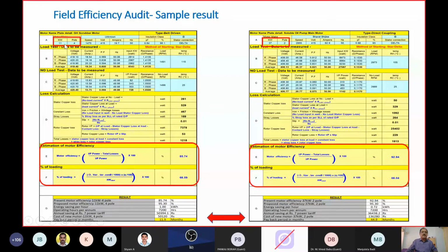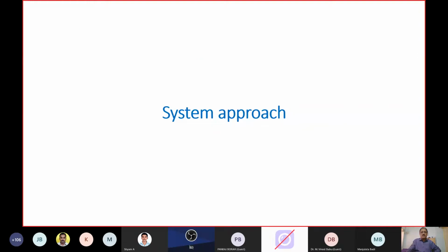In this case, it is an 11 kilowatt 4-pole motor. In this case, it's a 37 kilowatt 2-pole motor. It is possible to make on-site efficiency estimation and also project the payback estimate. Here it is 11.9 months. Here it is almost 45 months. So one could be persuaded to undertake on-site efficiency estimation and then shortlist the motors which could be replaced on a large scale basis. Anybody interested in this topic will have to get in touch directly so that we can discuss this further. Now let us go into the system approach.